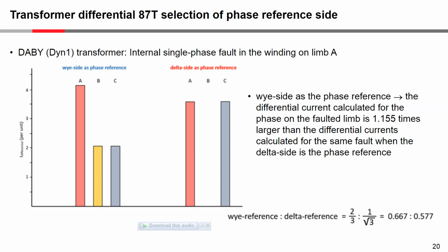So here's the comparison of the two. Remember the delta side, we had equal currents in A and C, okay? If we use the Y side as the phase reference, we had the highest current in phase A, lower currents or half currents in phases B and C, and also the differential current in phase A is higher than the differential current measured when the delta side is the phase reference, and it's higher by a factor of 1.155. And that comes from this here at the bottom right, which really reflects back to the matrices that are used.